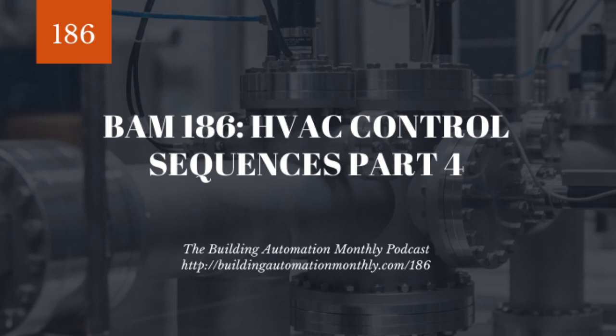Now, we can have variable volume with 100% outdoor air units, especially if we're serving operating rooms that have a supply box and an exhaust box in the operating room, and they are trying to manage a positive pressure scenario in the OR so that nothing can come in, right? We're pushing all the air out.